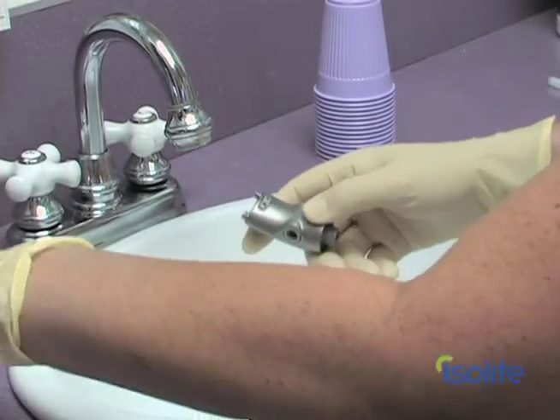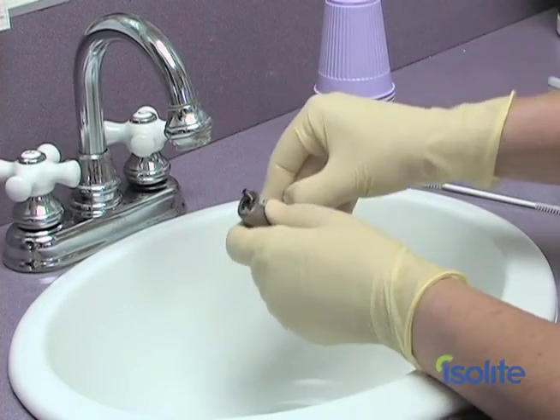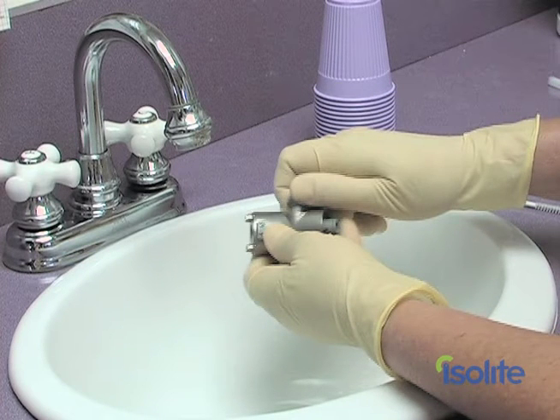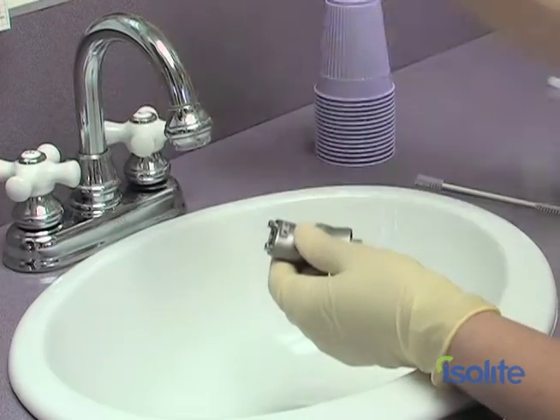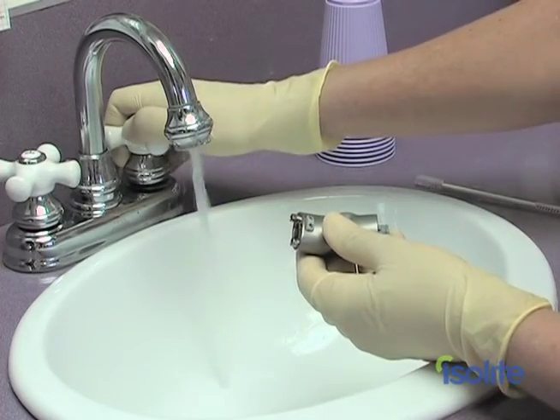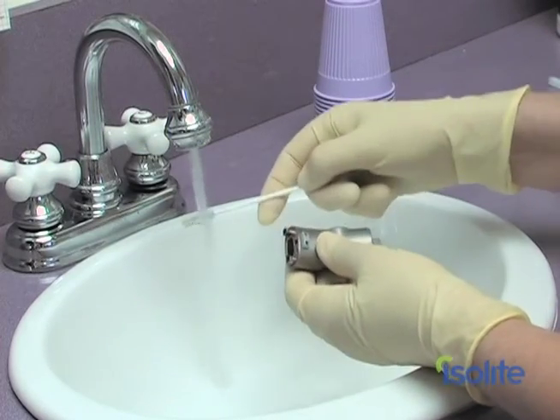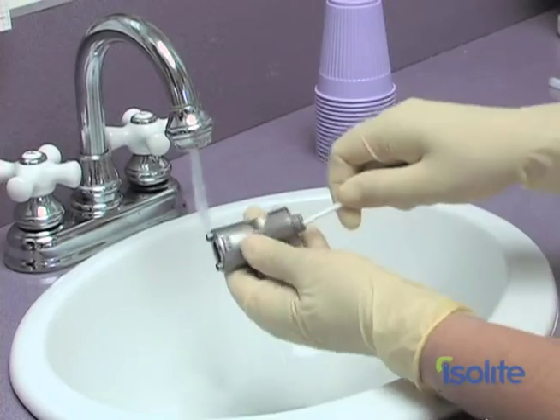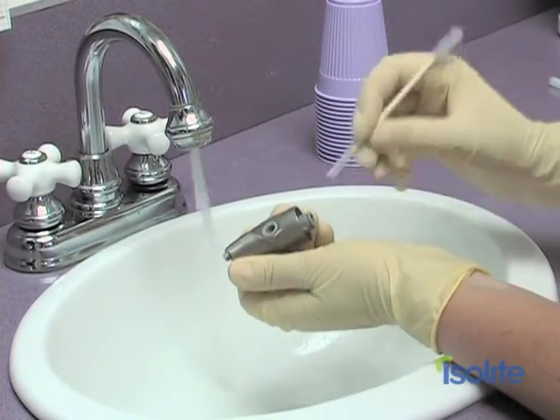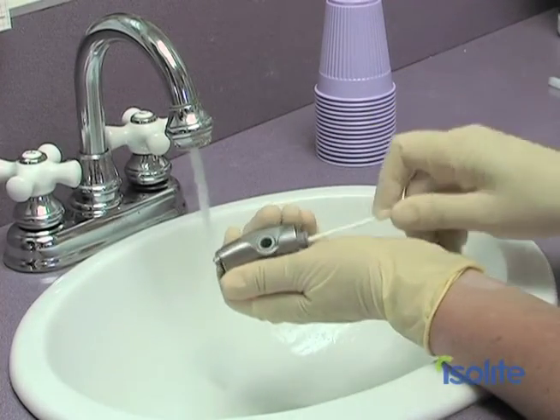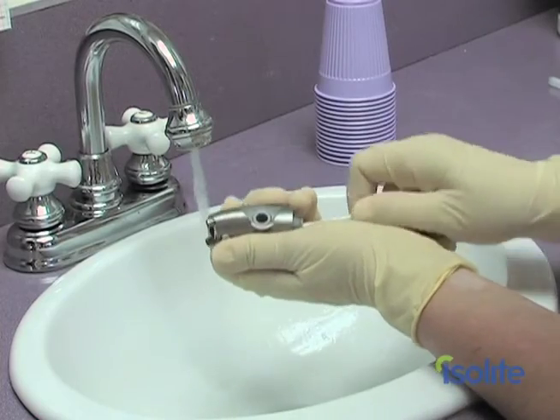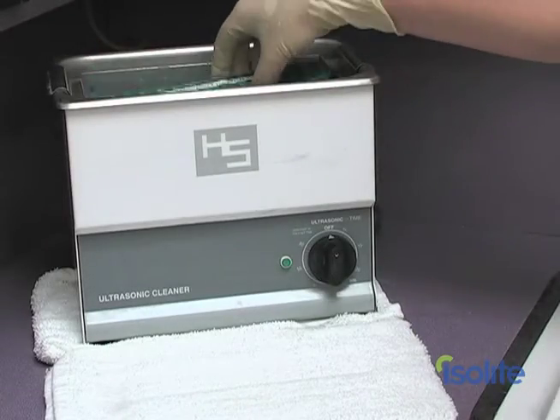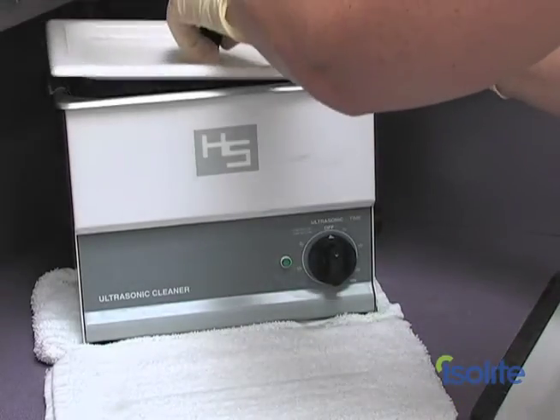To clean the titanium control base for either your Isolite or IsoDry, first remove the valve levers as shown here. Gently but firmly pull each lever directly out of its socket. To hand scrub, use the cleaning tubes provided with your Isolite system. Dislodge any biomatter in and around the lever socket and vacuum tubes as shown. Scrub and ultrasonically clean the main housing prior to sterilizing.